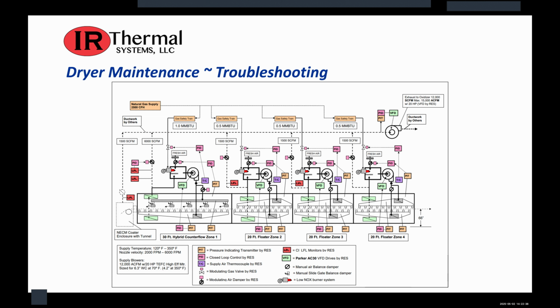I've even seen where people have taken our document and put together handbooks where they have each component, like a pressure transmitter in zone 1 might be Z1PT 105, and then 205, 305. That would carry through. This way, when engineering is working with maintenance, they can say, go to PT 305. Then the maintenance group can pull up this diagram and say, oh, I'm going to go to second floor, plenum 3, on the gear side, and they'll know exactly where that location is. And also, if they have it in conjunction with pictures to identify those parts, it can make maintenance a whole lot easier and avoid extended downtimes due to confusion.